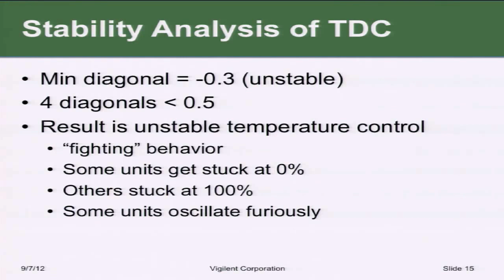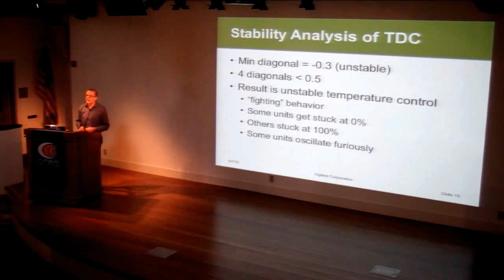You can just look at it, if you have a monitoring system, and see that's the case. You get lots of different behaviors from this kind of scenario. You get this fighting behavior where they're trying to overcome each other. And when they fight, some can drive others off. So you can have one of them cool, its cold air gets sensed by another one's temperature sensor, causing that one to shut off. It stays off until the data center gets so hot that cold air itself heats up enough to bring the other one on. Others get stuck at 100% because when some get stuck off, there's not enough capacity remaining to regulate temperature. And then often, they just oscillate furiously, thrashing and wearing out the equipment like mad, while operators are left wondering why. Compressors that are supposed to last 15 years are wearing out every year.